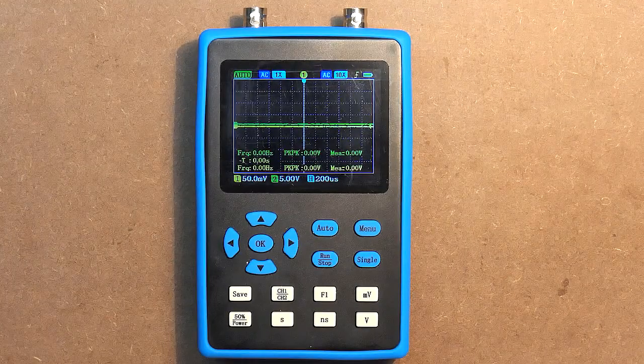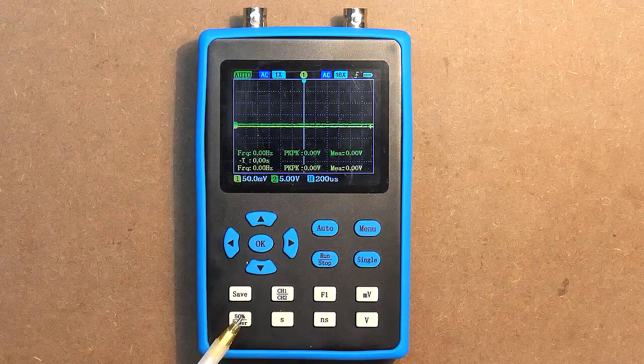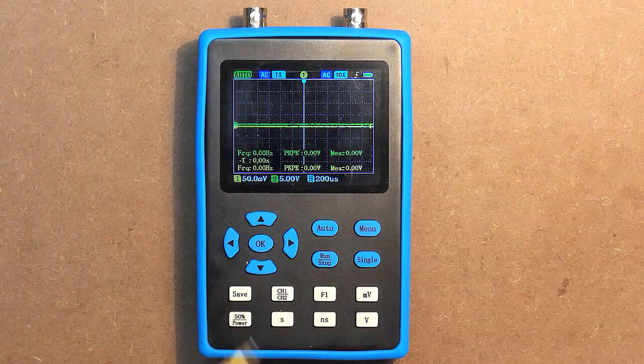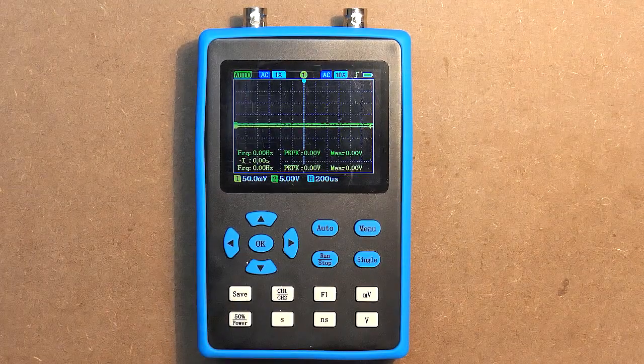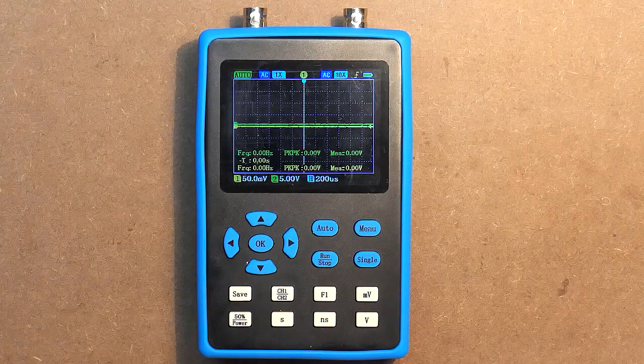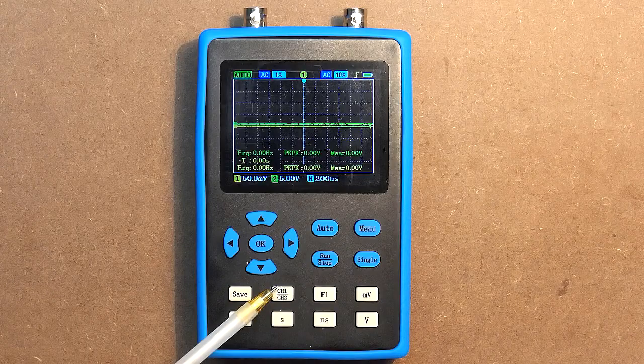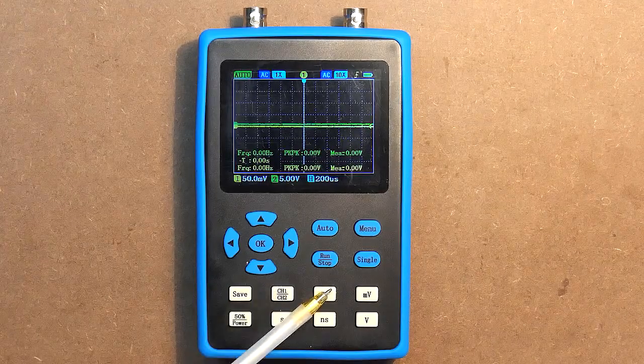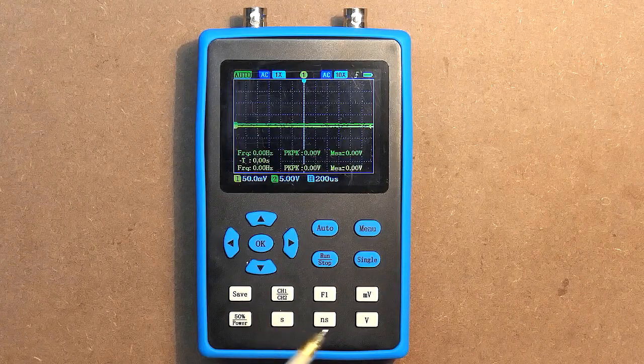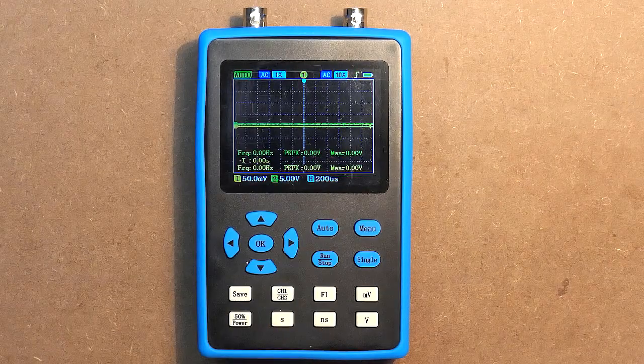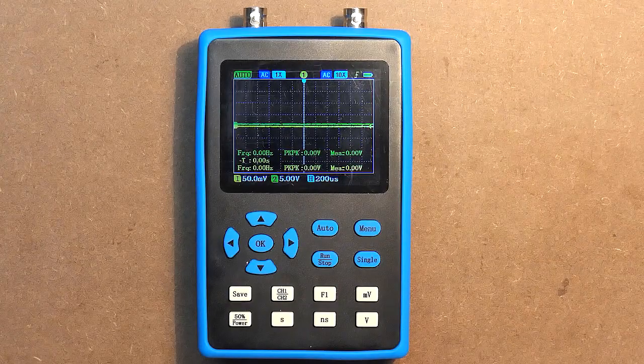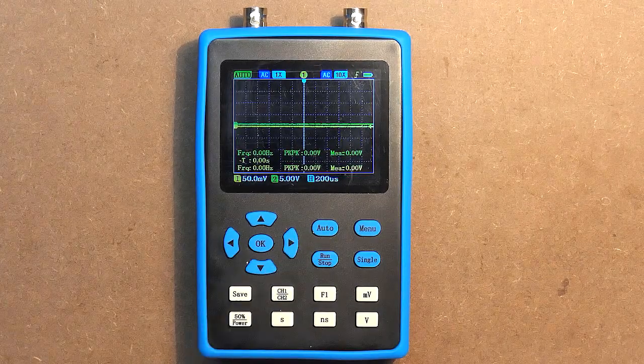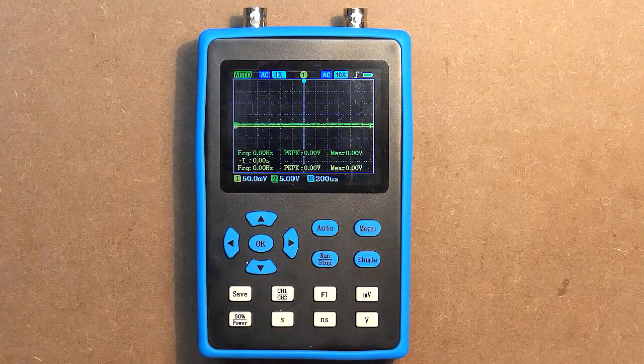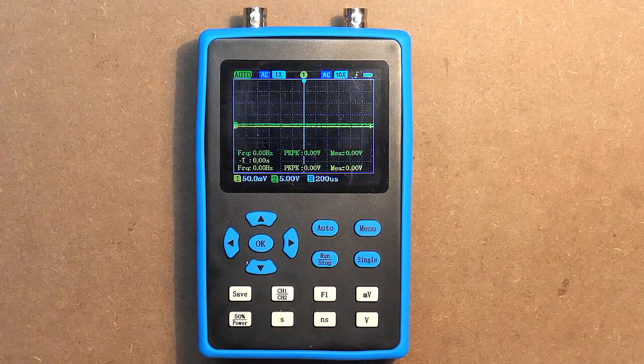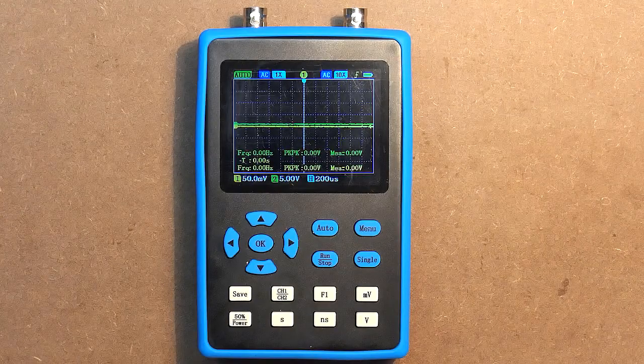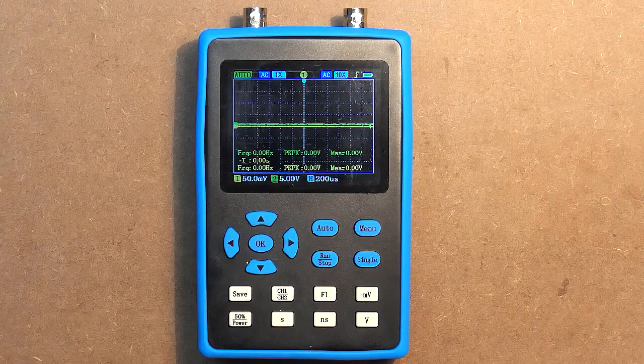Moreover, the manufacturer has made some changes and it's easier to use this two-channel oscilloscope in comparison with its single-channel brother. Here we have the power button, which is multifunction, or let's say a shift button at the same time. Save, we can save the graphs for subsequent transferring to the PC. We can switch the channels and even switch the second channel off. This is the signal generator button. Seconds, nanoseconds, horizontal sensitivity. Volts, millivolts, vertical sensitivity. Auto is auto adjustment. Menu is menu. Run/stop is used both for the oscilloscope and the signal generator, and also here we have a single button for single measurement.